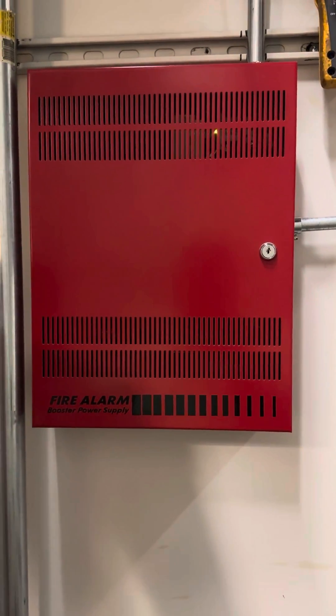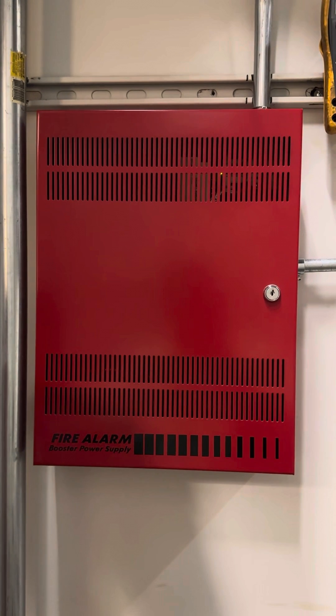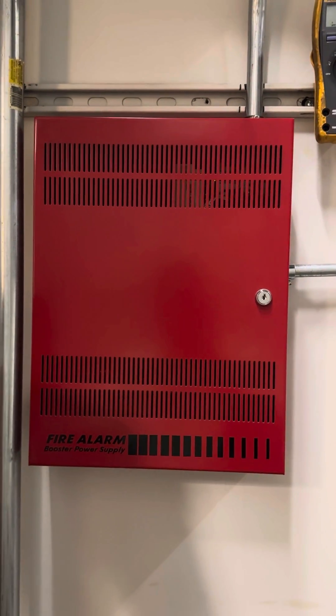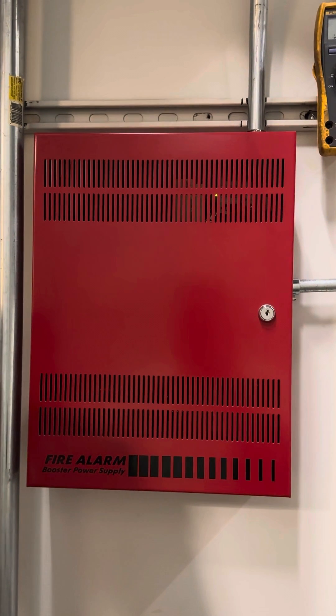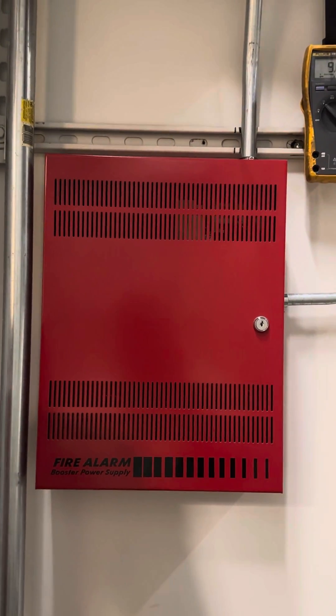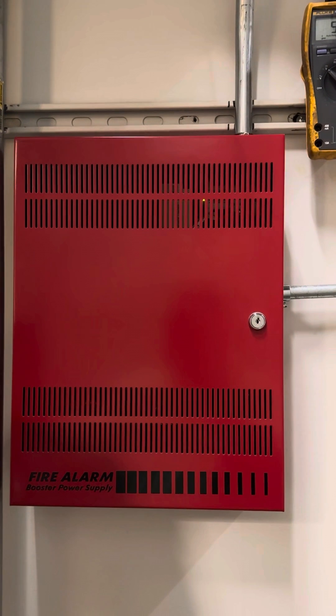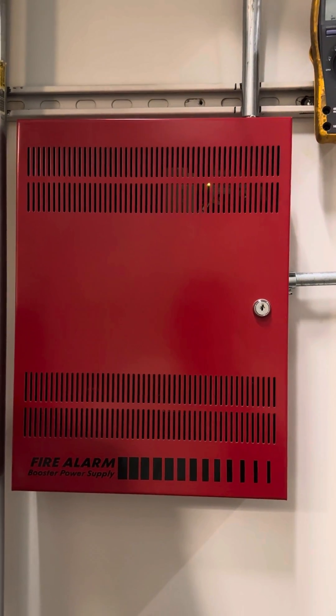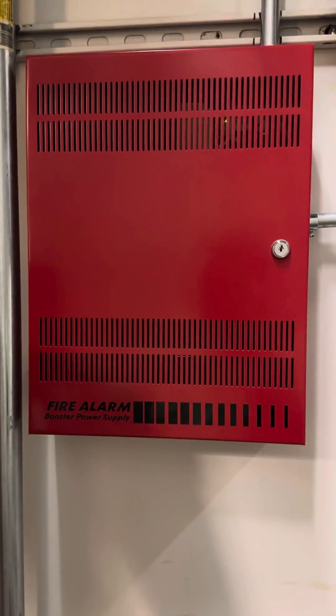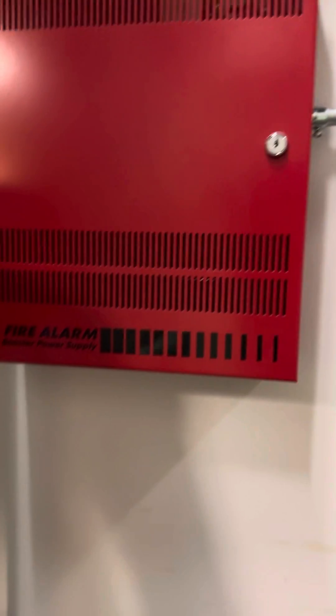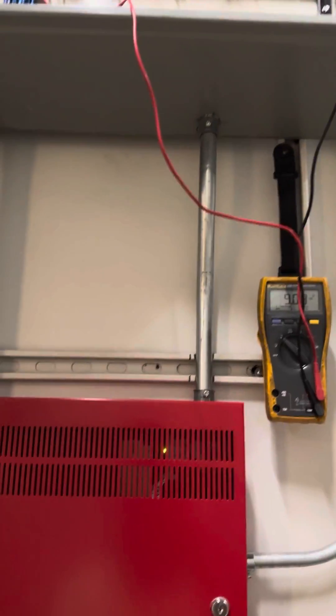What's going on everyone, so today we are troubleshooting an Edwards BPS. I have an issue where the 24 volts on the amplifier output is reading 9 volts. So typical scenario in a building like this, the devices go bad.